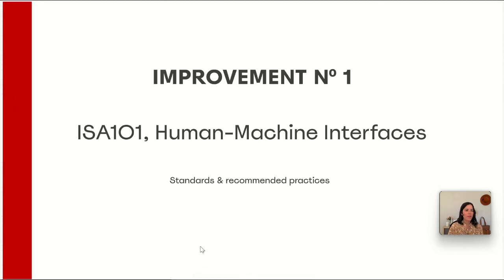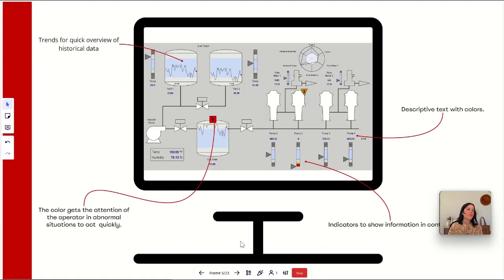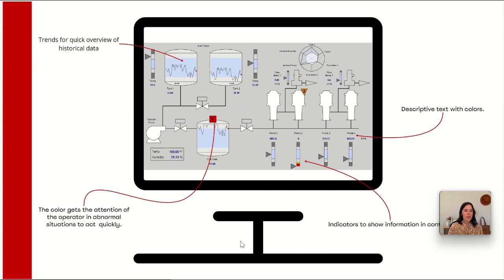We have improvement number one, which is the ISA-101 — the human-machine interfaces standard — that provides the standards and recommended practices to build a high performance HMI. The first thing you will notice when you are in front of a high performance HMI is that everything is now in grayscale colors.